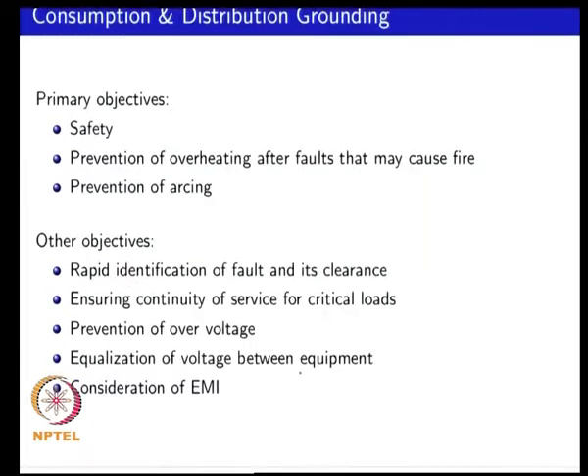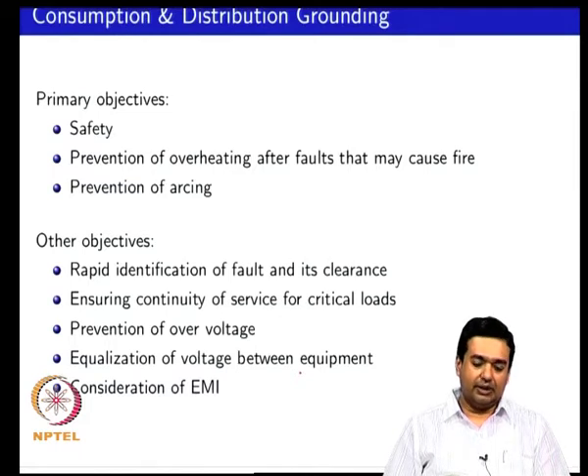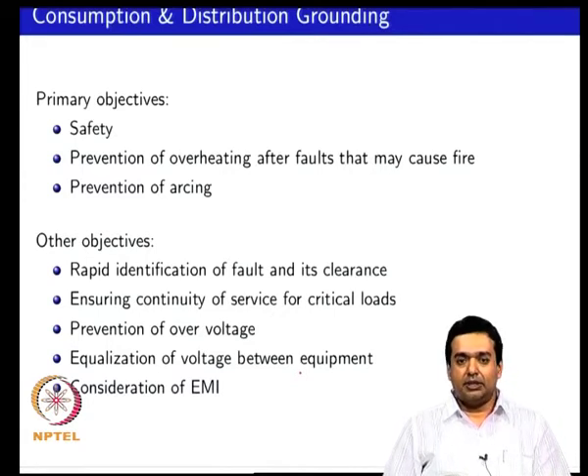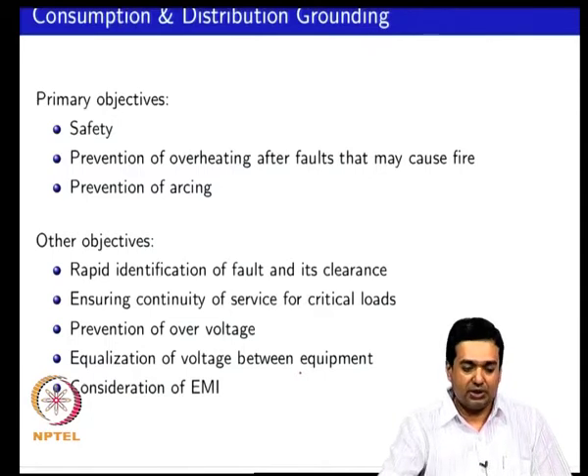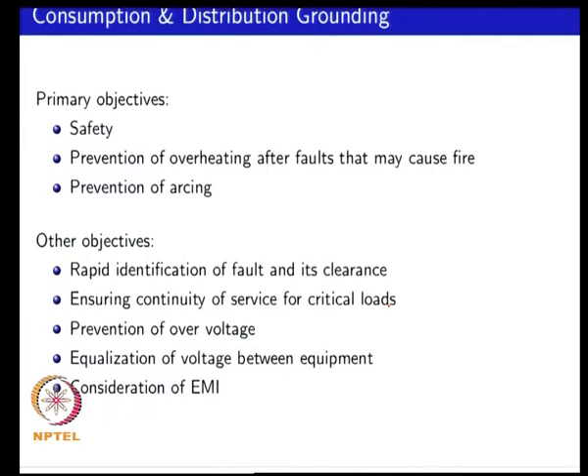Now we will look at another aspect of the distribution system — an important factor that also has implications when DG gets connected — and that is grounding. If you have any electrical system, you would ground it, and the primary objective of grounding is actually human safety. Someone should not touch the electrical system and get a shock or be electrocuted. So human safety is the primary objective. If you touch a cabinet, you should not get a shock, so you should have low touch potential.